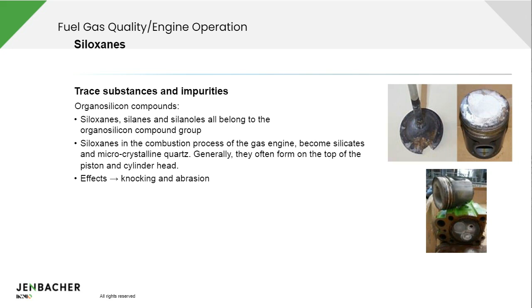Let's say some operators used to prefer to do more frequent maintenance on these parts and just replace them rather than treating the gas. But components in modern gas engines like Jenbacher's are really designed to last a long time. So if you're replacing these rather expensive pieces of equipment more frequently, then overall you're going to have a higher cost of operation than if you clean the gas. So definitely you'll want to clean the gas to avoid these issues, which are not only costly but also a reliability concern, as obviously the engine will go down once you have a situation like is shown in those pictures.